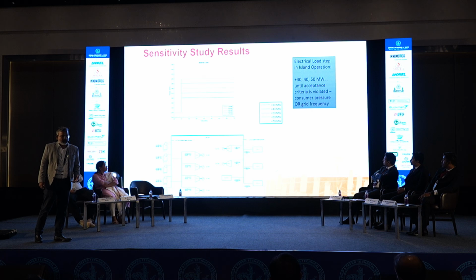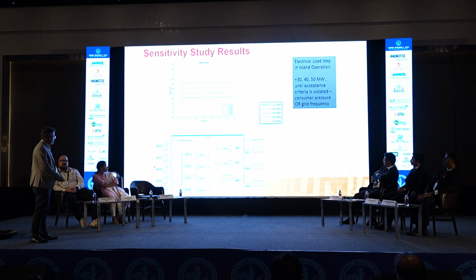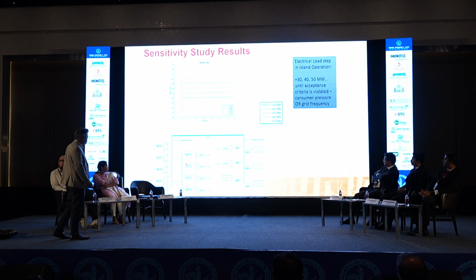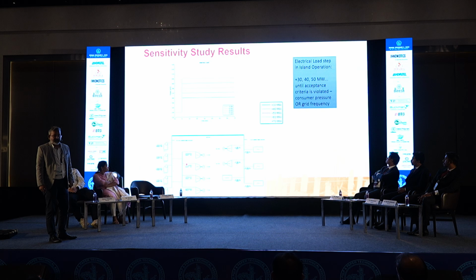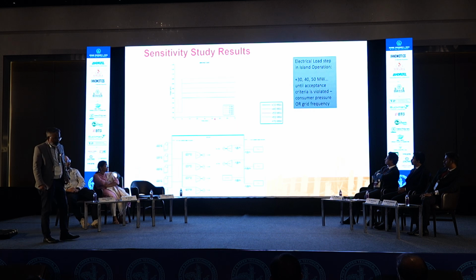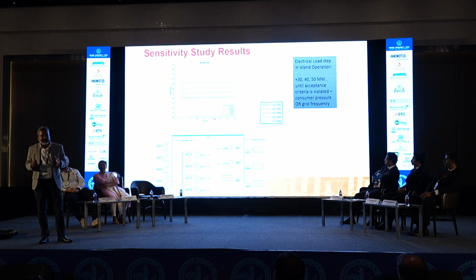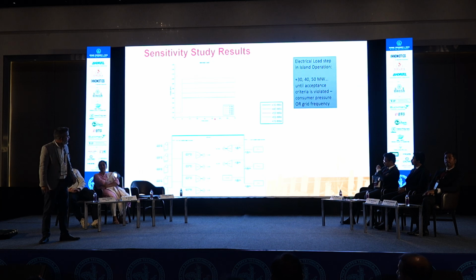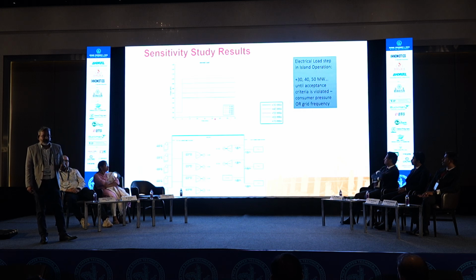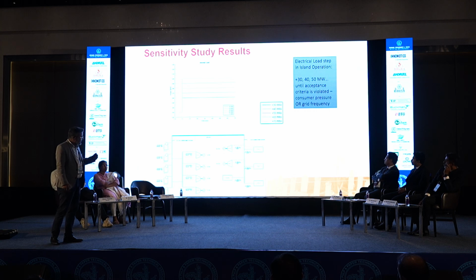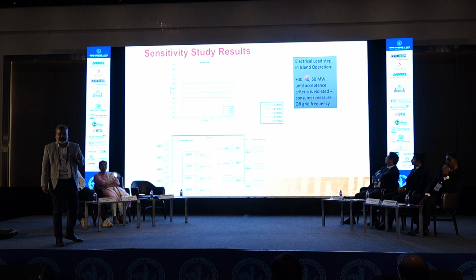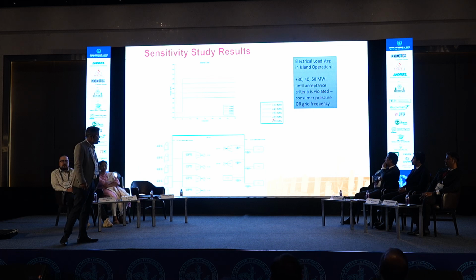Now, how do we do it? Our basic methodology is that we develop a complete dynamic model of the entire plant, including the boilers, turbines, the entire steam distribution network, as well as the entire electrical control system network, along with all the consumer units like PTA 1, 2, 3, and cracker units. Once we have a dynamic model which closely replicates how your real system would be, we start with sensitivity studies where we give load steps to the system. We start with smaller steps and gradually increase them to see up to what load handling limits the system will survive and up to what limit it will fail the acceptance criteria.